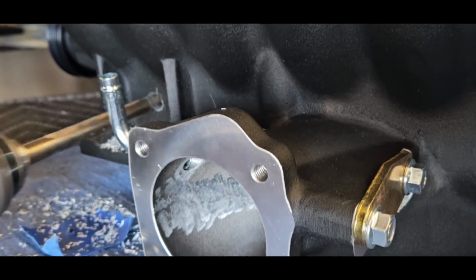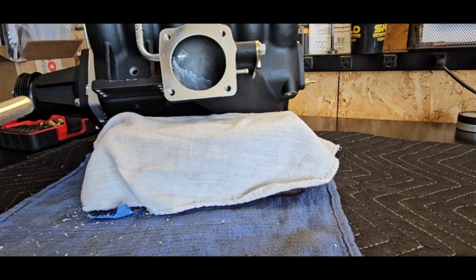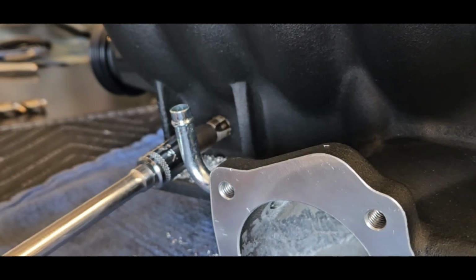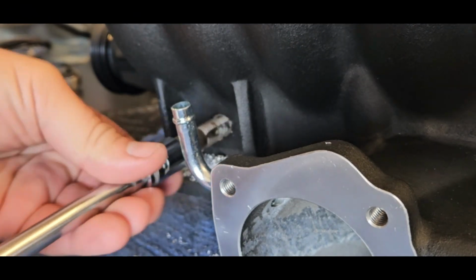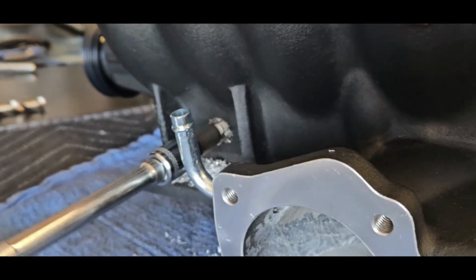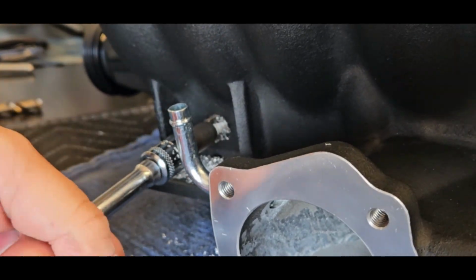This particular installation, we're using a 1/4 20 air temp sensor. Normally we'll do a 1/8 inch NPT, sometimes a 3/8 NPT, depending on what sensor we're using and where we're getting it from. As long as we have a sensor calibration, that's all that really matters.